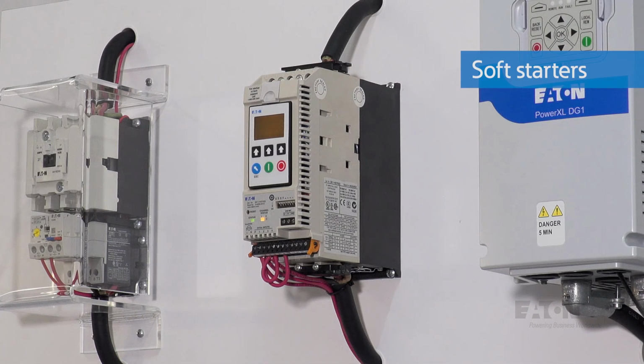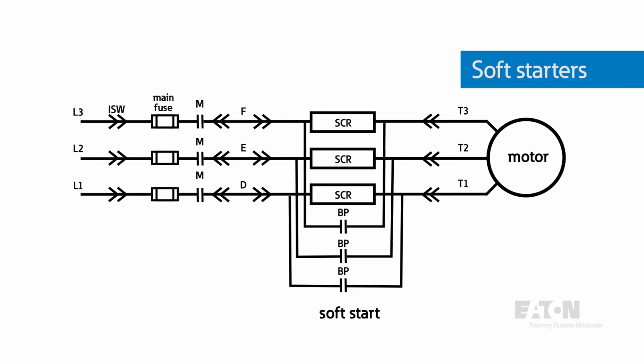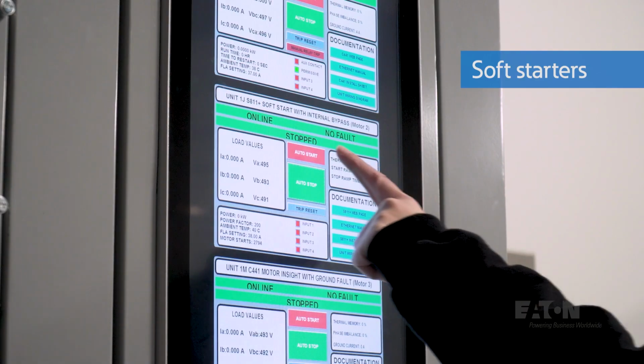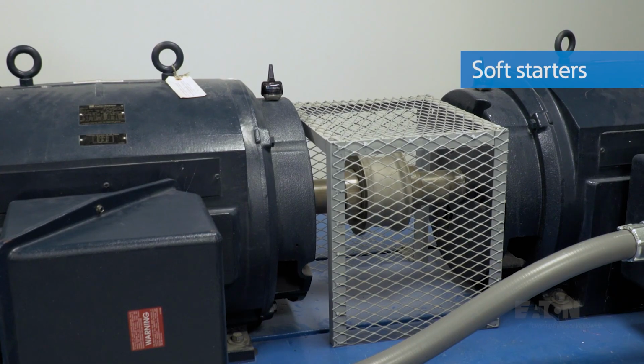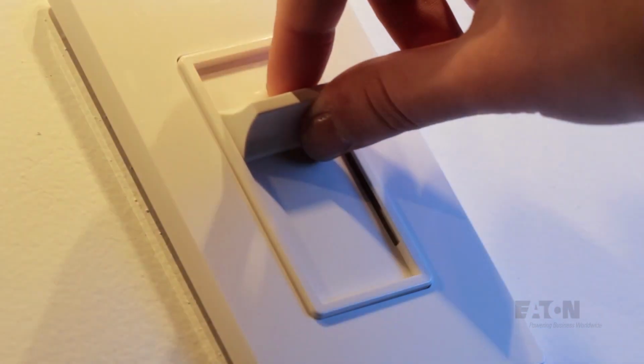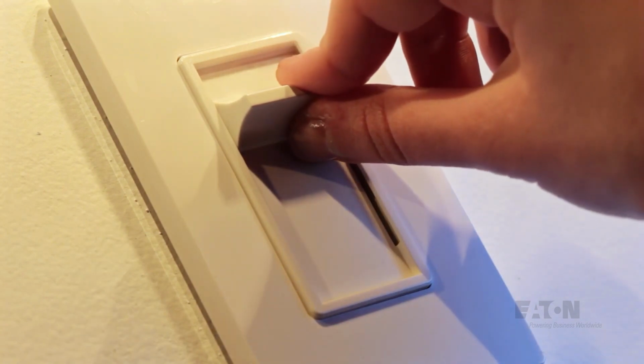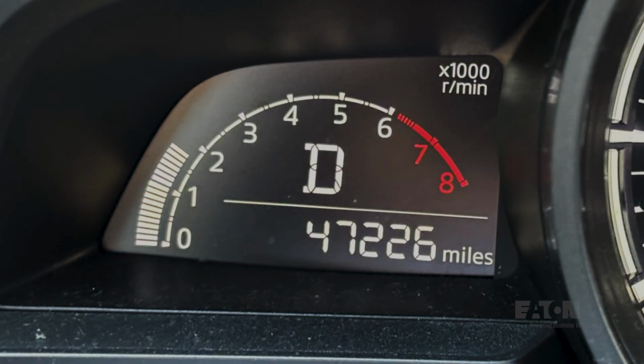Soft starters reduce the inrush current of the motor by pulsing the voltage on with power electronics, usually SCRs, ramping the RMS level from 0 volts to full voltage. Using the light analogy, this would be like adjusting a dimmer from off to full on and then leaving the light on at full output. The soft start would be like slowly accelerating your car with a gas pedal, pushing it all the way to the floor and then driving your car at full speed.